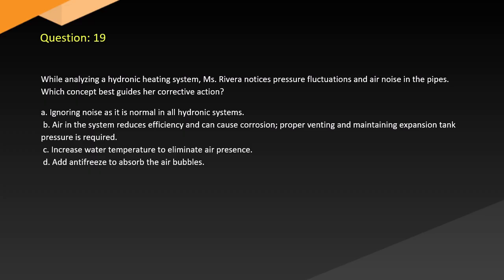Question 19. While analyzing a hydronic heating system, Rivera notices pressure fluctuations and air noise in the pipes. Which concept best guides her corrective action? A. Ignoring noise as it is normal in all hydronic systems. B. Air in the system reduces efficiency and can cause corrosion. The proper venting and maintaining expansion tank pressure is required. C. Increase water temperature to eliminate air presence. D. Add antifreeze to absorb the air bubbles.